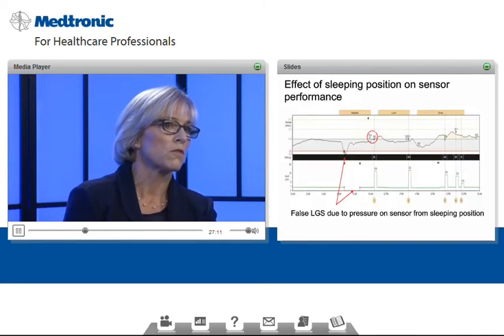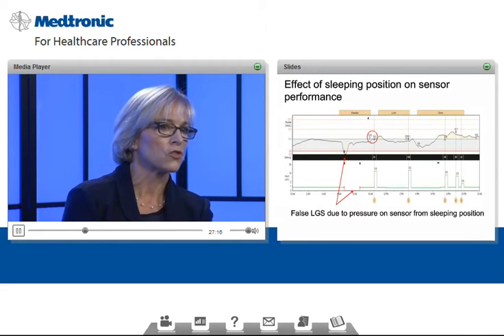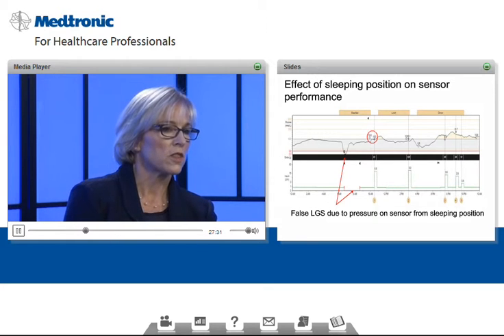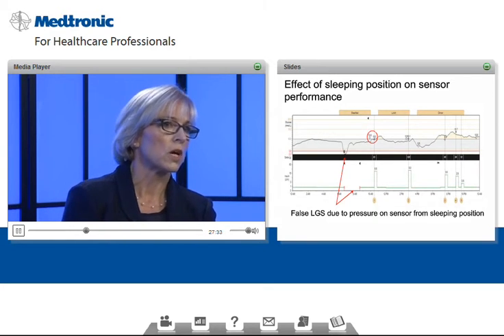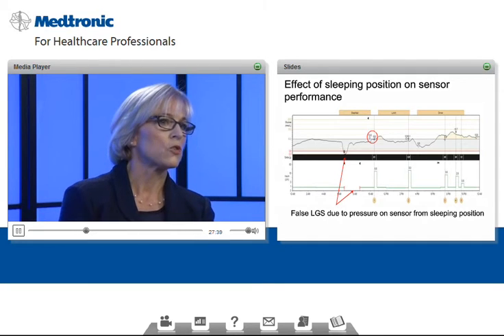And this was shown in one of our patients, where you can see here the sensor is quite stable through the night, and then you see this sudden drop around 6 in the morning, where it looks like the glucose drops precipitously, which would not be expected or explained. That triggered a false glucose suspend alarm, and the blood sugar rose when the individual didn't check their blood sugar and confirm that it truly was low. And so we advise our patients to make sure that they choose a sensor location that is away from the place they usually sleep.